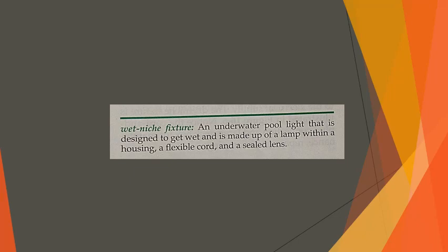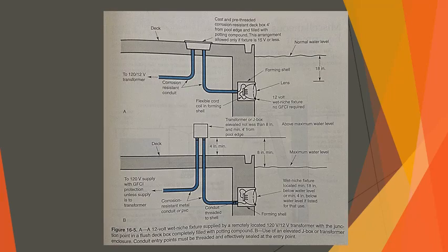Raceway between the fixture and the junction box or transformer for low voltage fixtures must be either rigid or intermediate metal conduit made from brass or other approved corrosion resistant metal, liquid tight flexible non-metallic conduit, or rigid non-metallic conduit having an 8 AWG insulated copper conductor to connect between the fixture and the junction box or transformer enclosure. Wet niche fixture.